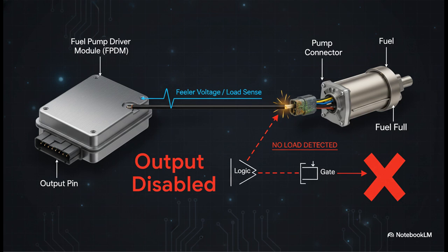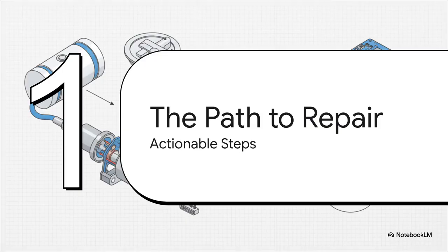But if your connector is junk, it's corroded, full of crud, or maybe it's just not clicked in all the way, the FPDM sees nothing. It sees an open circuit. To the module, that means no load, and it immediately says, whoa, something's wrong, and it shuts down the power of that circuit to protect itself. No load, no power.